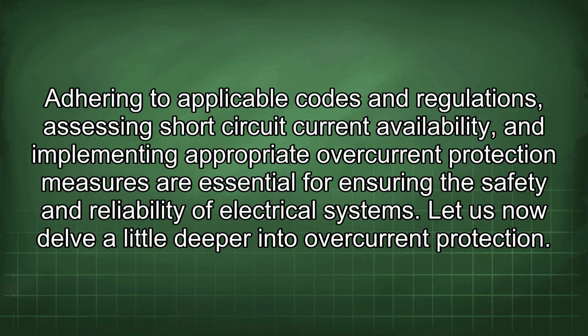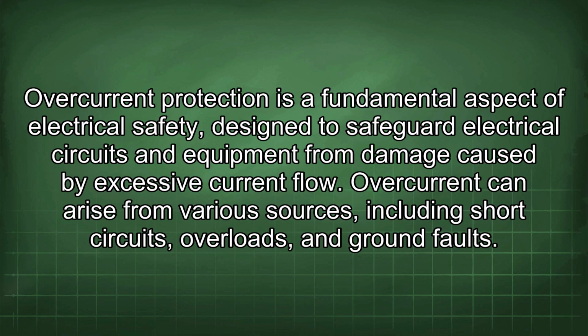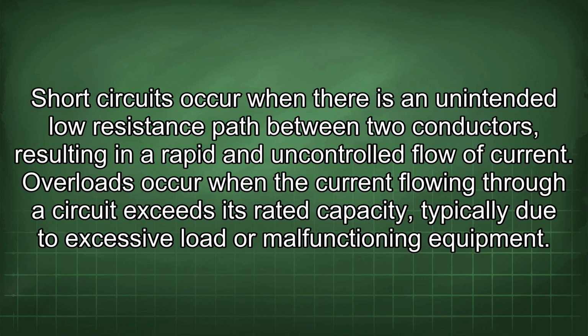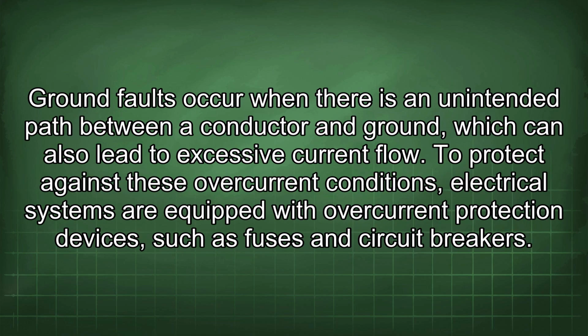Let us now delve a little deeper into overcurrent protection. Overcurrent protection is a fundamental aspect of electrical safety, designed to safeguard electrical circuits and equipment from damage caused by excessive current flow. Overcurrent can arise from various sources, including short circuits, overloads, and ground faults. Short circuits occur when there is an unintended low resistance path between two conductors, resulting in a rapid and uncontrolled flow of current. Overloads occur when the current flowing through a circuit exceeds its rated capacity, typically due to excessive load or malfunctioning equipment. Ground faults occur when there is an unintended path between a conductor and ground, which can also lead to excessive current flow.